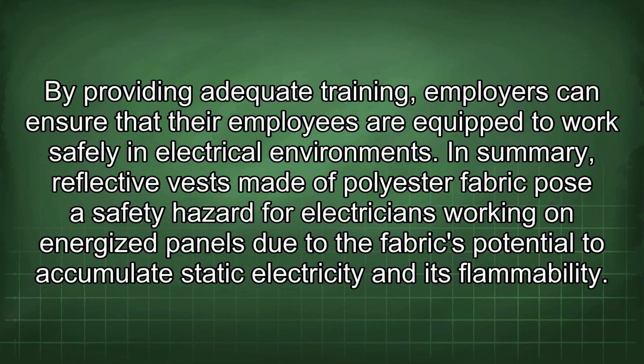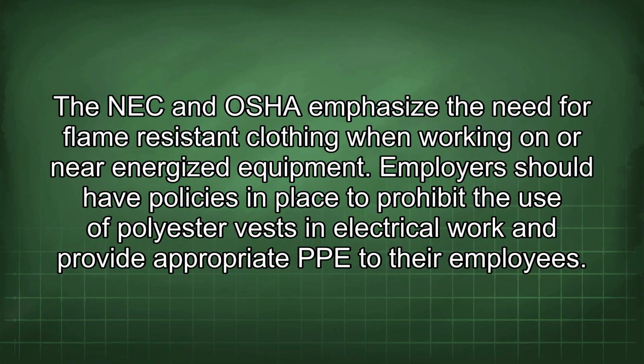In summary, reflective vests made of polyester fabric pose a safety hazard for electricians working on energized panels due to the fabric's potential to accumulate static electricity and its flammability. The NEC and OSHA emphasize the need for flame-resistant clothing when working on or near energized equipment.